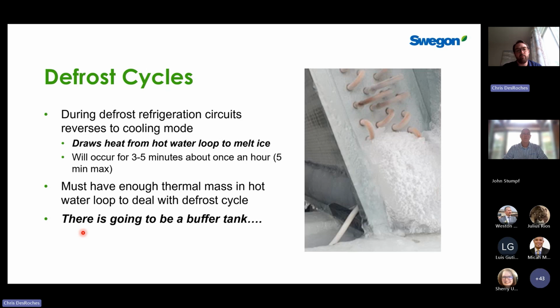So as you know, if we're producing heating from any kind of heat pump, in order to extract heat from outside, we need to send refrigerant to the coil outside that's colder than whatever the temperature is outside, so that we get heat to transfer from the air into the refrigerant circuit, and through the work of the compressor, we're boosting that up and making hot water on the outlet.